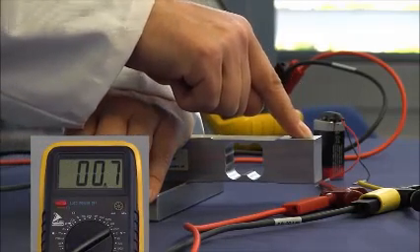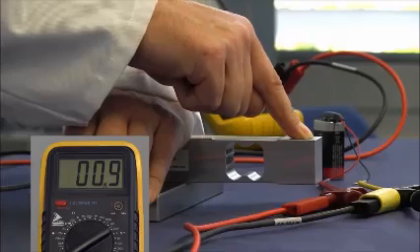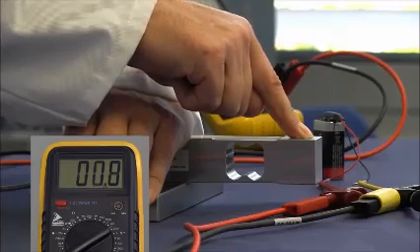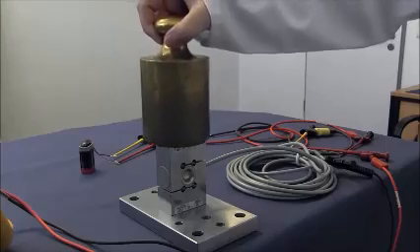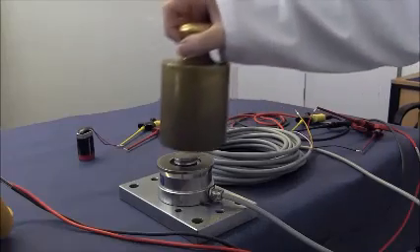If this is not the case, the load cell might be defective and should be further checked using an amplifier suitable for strain gauge transducers. Our simple test can be performed with a wide range of load cell types.